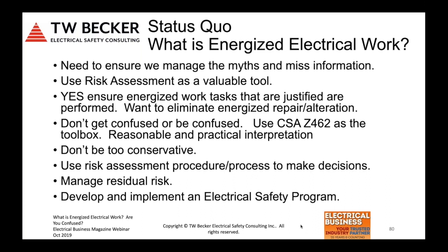We want to eliminate energized repair and alteration. That said, if we do have justification, we can use the energized electrical work permit process in 70E or Z462. The energized electrical work permit is not required to be used with every energized electrical work task. Unfortunately, this is another myth that I hear, right? So understand when the permit's required, when it's not, what the exemptions are. And in my opinion, in your company's documented electrical safety program, you can take additional exemptions that are valid.